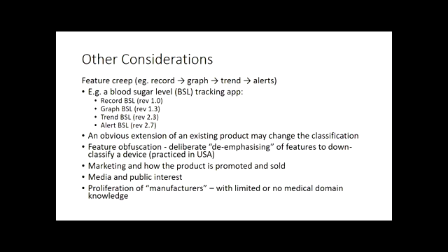Most of the time you won't get pulled up on it as long as you're actually really clear that it's not a medical device. So it's all about language. If you say it's an aid in the diagnosis of, or it's a tool to help the clinician decide X, Y, and Z, then it's not a device. But if you say it will give you a diagnosis, then it is. Yeah, it's a bit iffy. And all they can do is ask you to withdraw your device. You can get sanctions and fines, but I don't actually know of any happening recently.